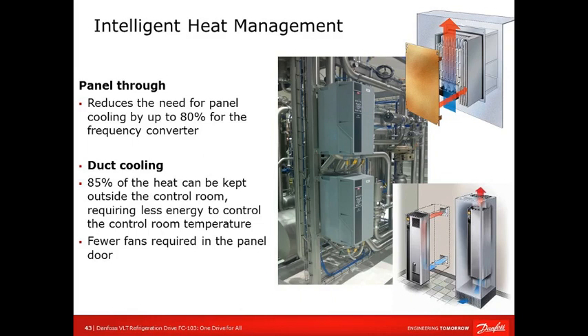In the bottom picture, we're showing some flexibility where you can mount the VFDs up to 350 horsepower. You can mount them on the wall, actually. Side-by-side, book style, you don't need any separation. And you can direct airflow outside the mechanical room, for example, and go across the heatsink and back out. The bottom right picture shows the alternative, where Danfoss has a little pedestal kit, with airflow going in the bottom and the heat dissipating from the top.